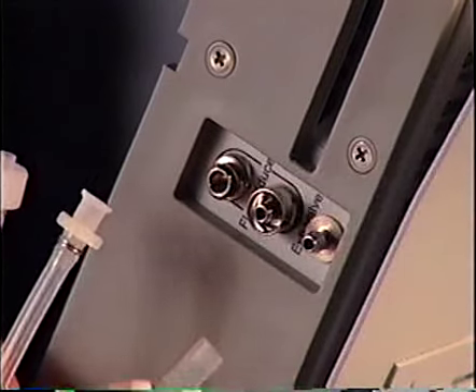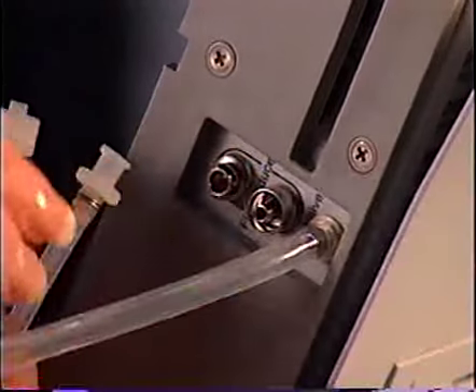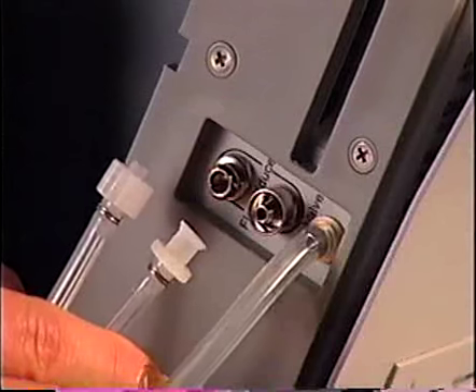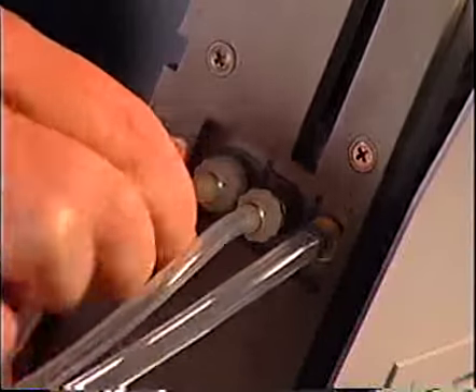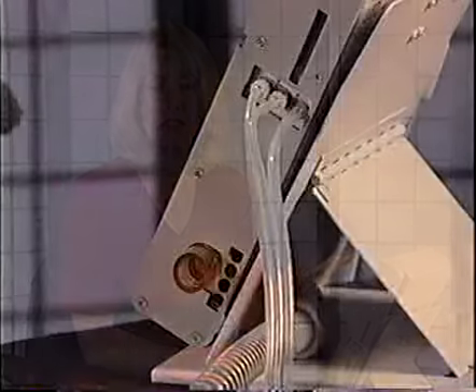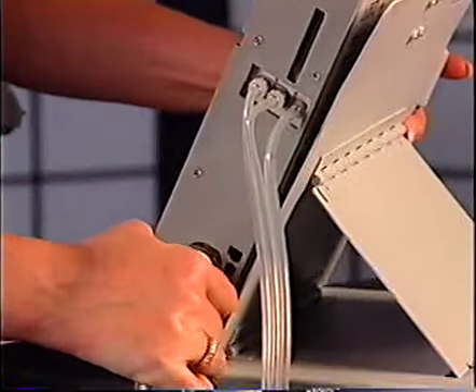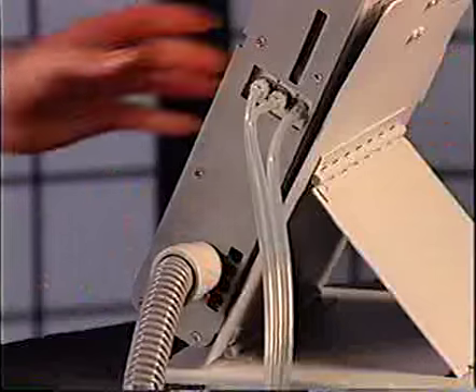The exhalation drive line is connected to the bottom port. The two transducer sense lines are non-interchangeable Luer fittings. Note that it is important to orient the sense lines up while the ventilator is operating. Keeping the sense lines up will help keep them free from fluid and debris. For the first minute that the LTV is turned on, a bolus of air is sent through the sense lines with each breath. After the first minute of operation, a bolus of air is sent through the sense lines once per minute. To complete attachment of the patient circuit, connect the end of the circuit to the 22 mm outlet port.